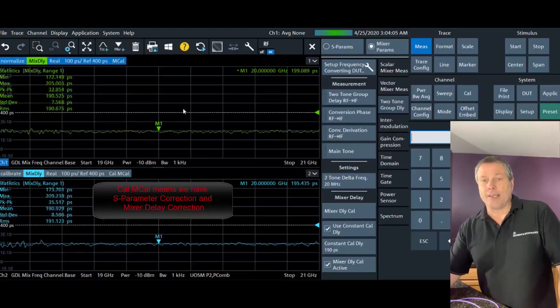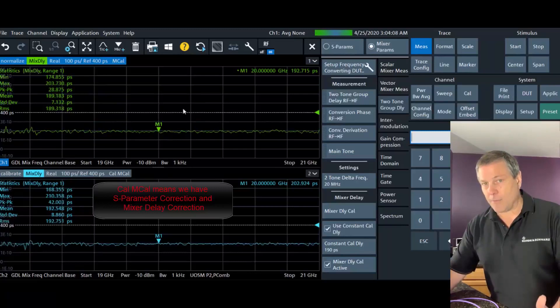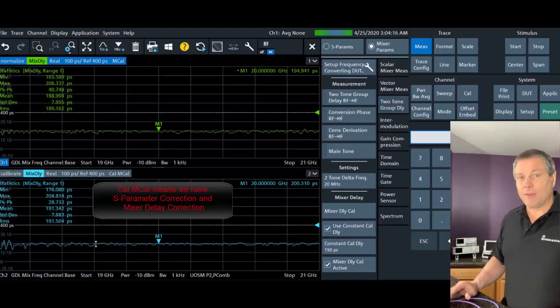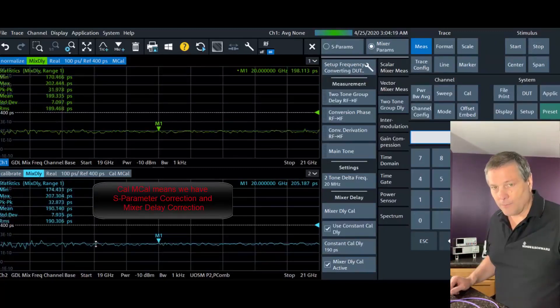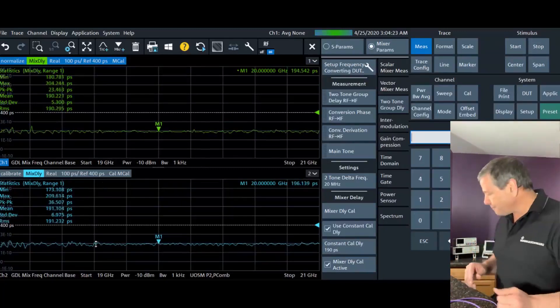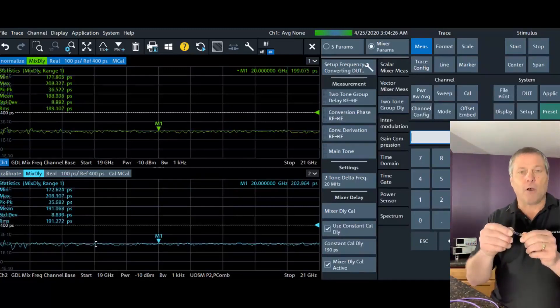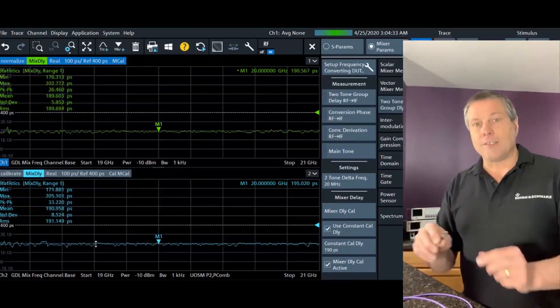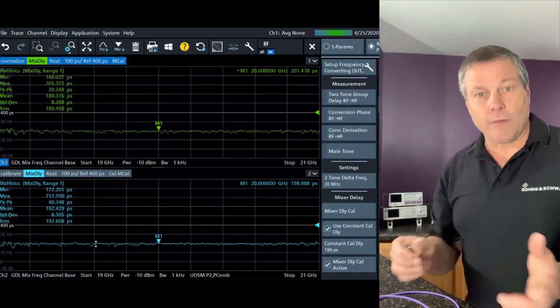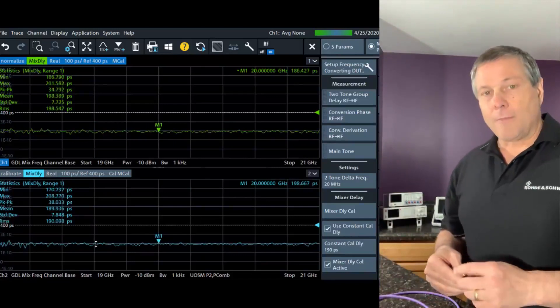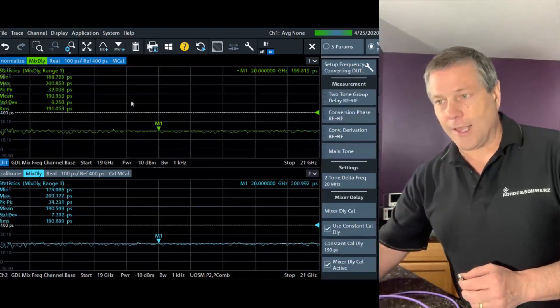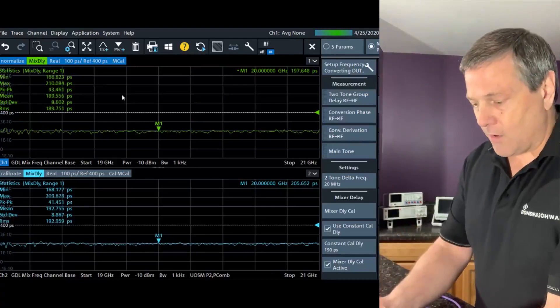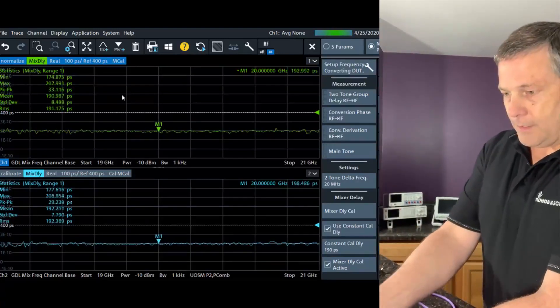The drawback of channel 1 is that any mismatch change occurring between calibration and measurement will show up in the trace, whereas channel 2 will correct for mismatch and minimize the effect. The next step is to add a small piece of transmission line to the output of the calibration mixer — as we did in video number 9. This will cause the output return loss to rotate on the Smith chart to a different location. It will still be a good return loss, but with a different reflection angle. On the normalized channel 1, this will cause ripple in the results, while channel 2 with the error correction model should show lower ripple.